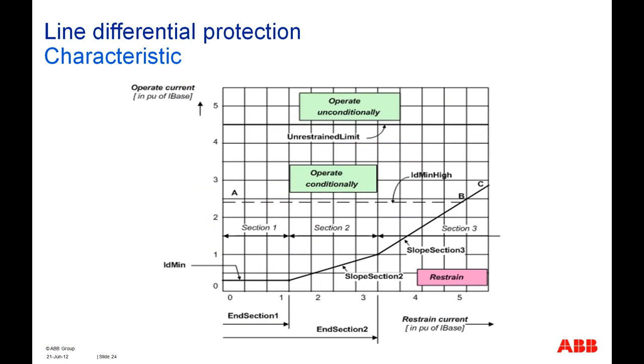So this is the line differential characteristics. Here we can see it's essentially the same characteristics which we have seen before in the earlier slides. But some additional information is mentioned in here. So it starts from slightly above the origin, and this margin, ID min, or the minimum differential current value, is also a setting in RED 670. RED 670 is the line differential protection device. So it starts a little bit higher than the origin, and that is to cover the inherent inaccuracies of the CTs, and then it ends.